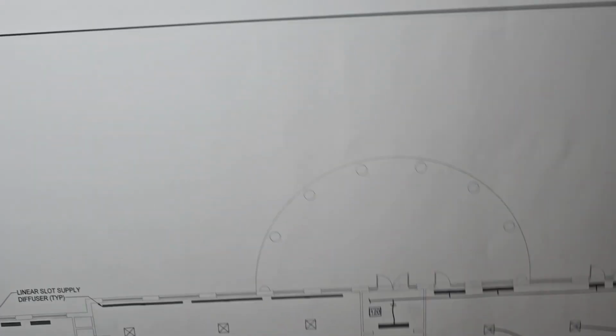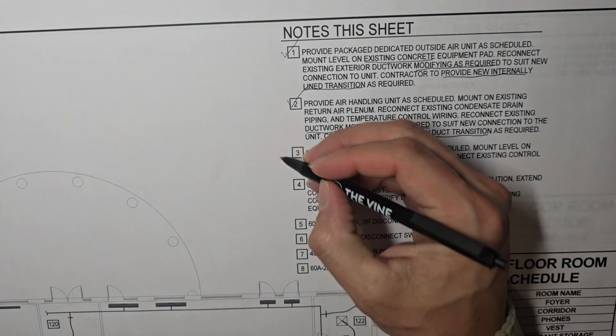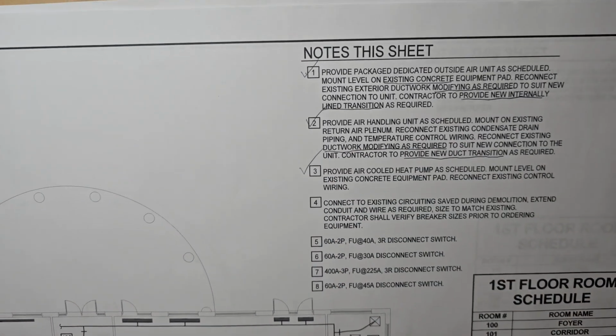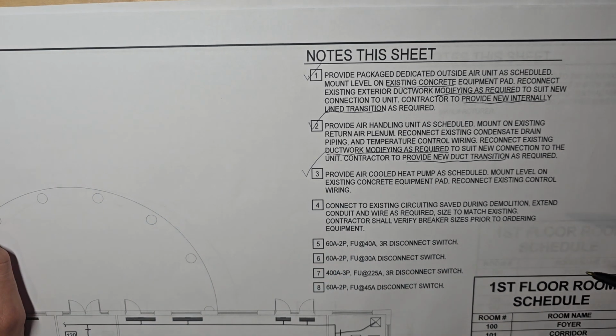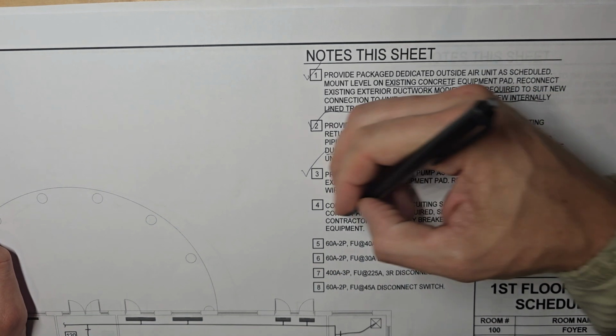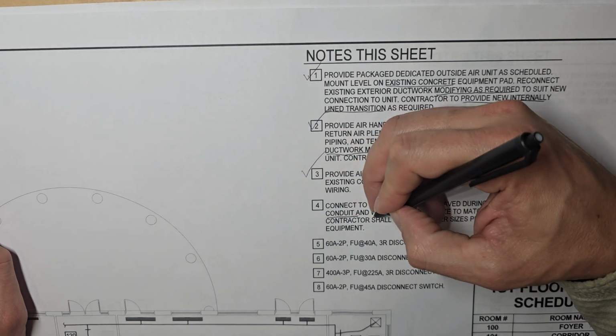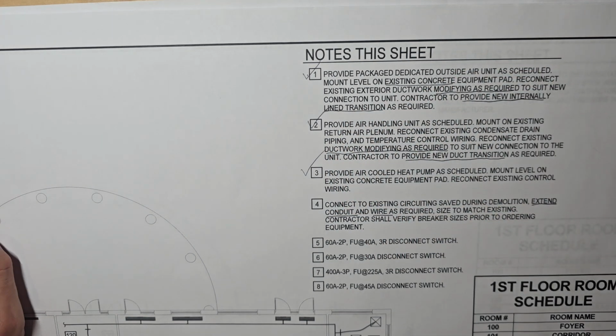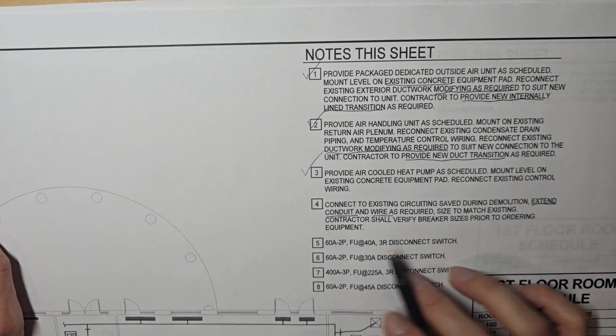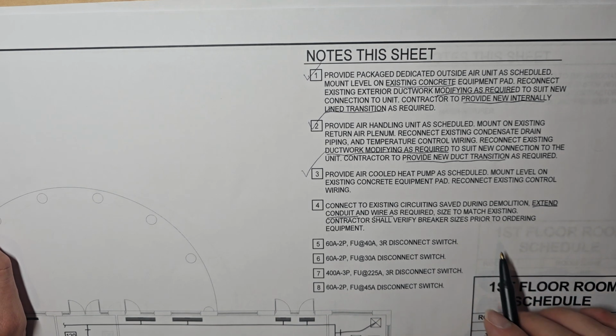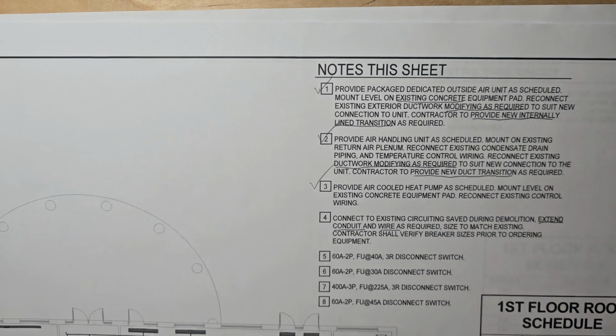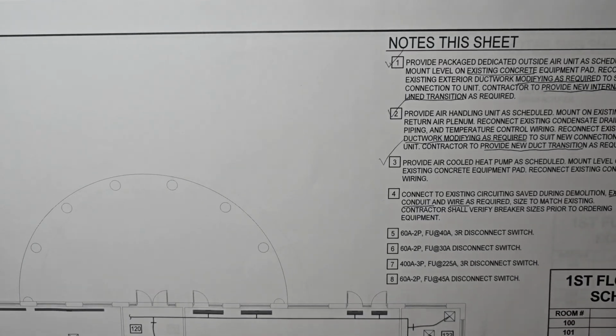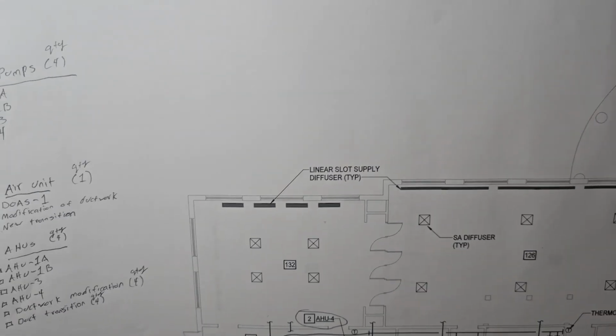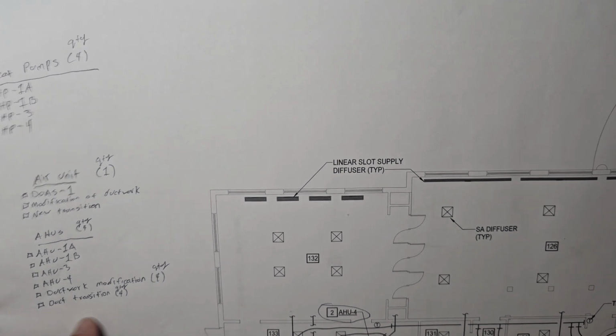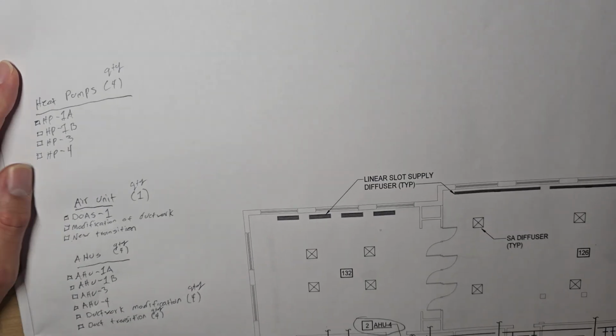All right, that's those. Connect to existing circuiting, saved during demolition, extend conduit and wire as required. So we're gonna make a note for this. Size to match existing, contractor shall verify breaker sizes prior to ordering equipment. So we need to make a line item for extend conduit and wire as required. So each one of these needs that added to it.